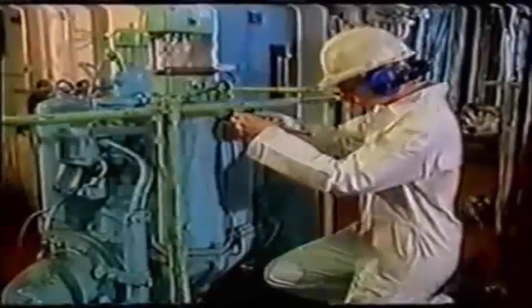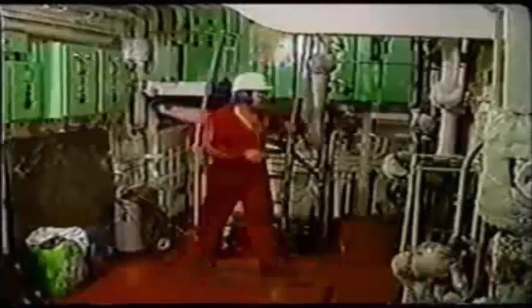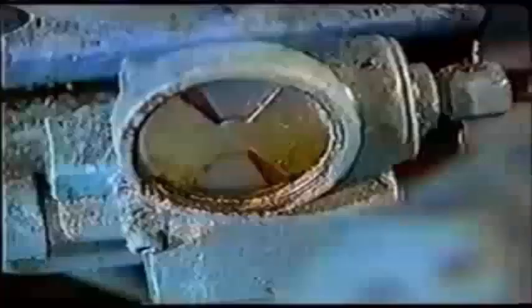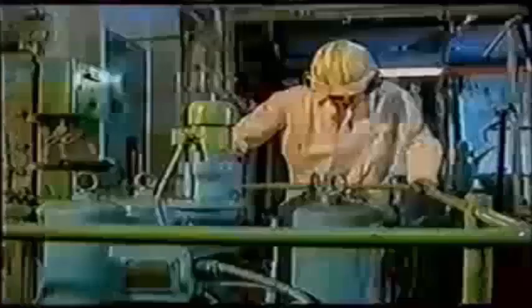Besides lubrication, the lubricant will transport contaminants and metal particles as it circulates, which then need to be removed. This is best achieved in a centrifugal separator, working in bypass, drawing oil from the oil drain tank and returning it there after cleaning. The application of inline filters also helps to remove some of the contaminants.